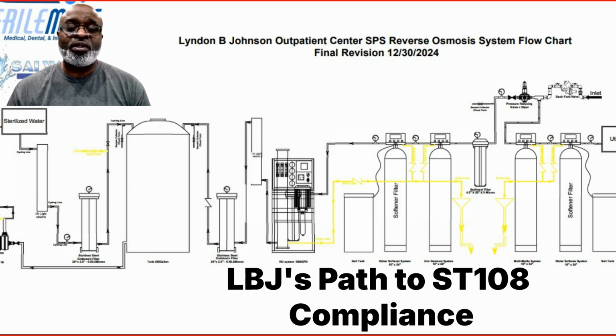This pathway includes a backflow preventer, which prevents water from reversing into the incoming water line. Sediment filter, removes large particles. Carbon tank, eliminates chlorine. Water softener, reduces hardness. Reverse osmosis system, removes bacteria and toxins. UV light and endotoxin filters ensure purity by killing and capturing bacteria. Critical water loop, circulates water for consistent quality.